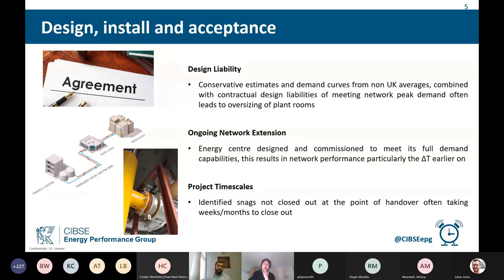Then we move on to how networks get delivered and installed. Generally, new build energy centers and district heating networks are designed and delivered based on their final peak demand. This leads to big kit being put into energy centers at the start of the network. In the early years of operation, with lower occupancy of the flats and further extension of the network, district heating particularly struggles with the delta T parameter.